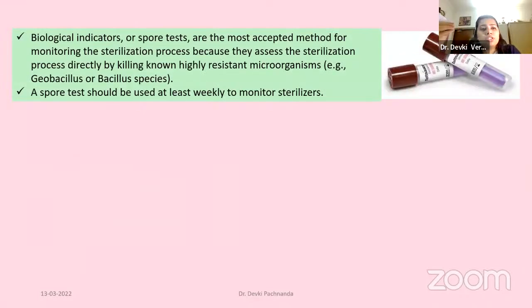Now, if you look at the biological method, biological indicators or spore tests, as they're called, I've put a picture alongside, are the most accepted method for monitoring sterilization as a process. Because it will show that when the autoclave has been shut or when the ETO is being done, it has reached a particular temperature and pressure for a particular time, by killing the heat-resistant microorganisms, which is Geobacillus or Bacillus, that is instilled in these small tubes. So the spore test should be done weekly.